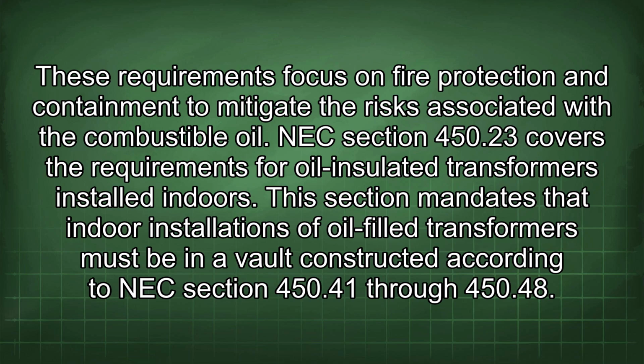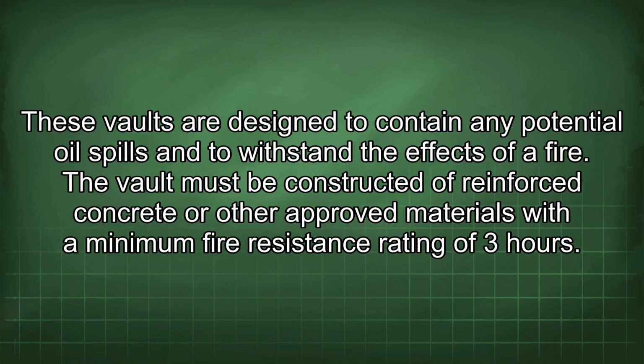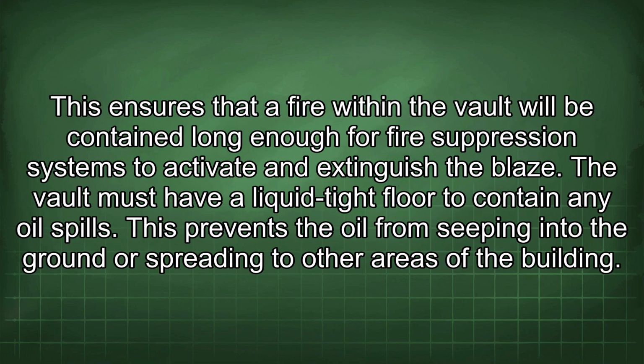through 450.48. These vaults are designed to contain any potential oil spills and to withstand the effects of a fire. The vault must be constructed of reinforced concrete or other approved materials with a minimum fire resistance rating of 3 hours. This ensures that a fire within the vault will be contained long enough for fire suppression systems to activate and extinguish the blaze. The vault must have a liquid-tight floor to contain any oil spills. This prevents the oil from seeping into the ground or spreading to other areas of the building.